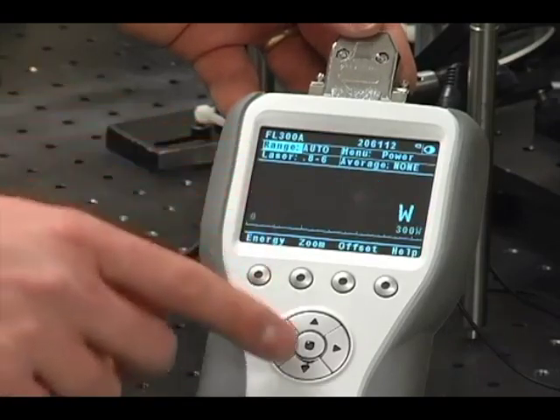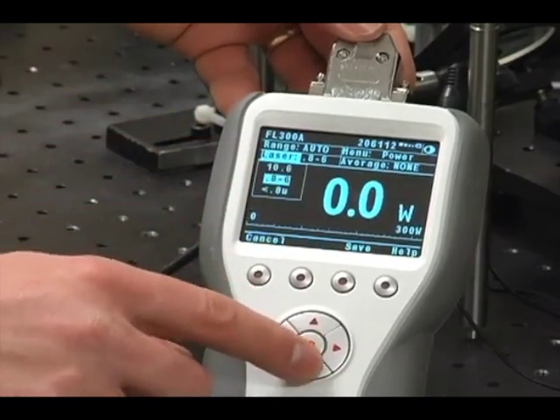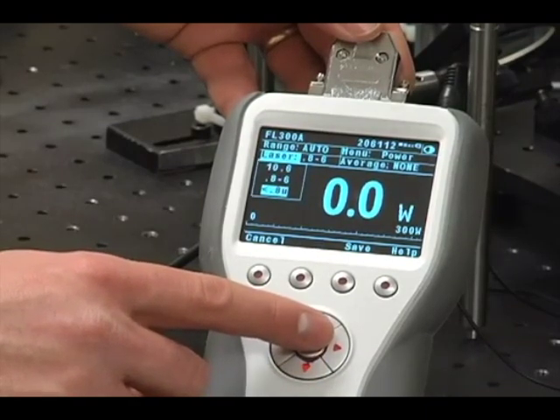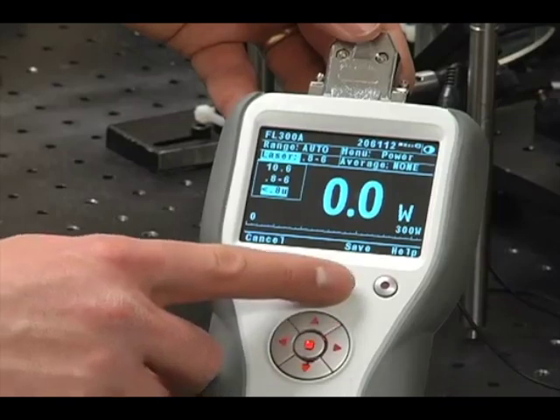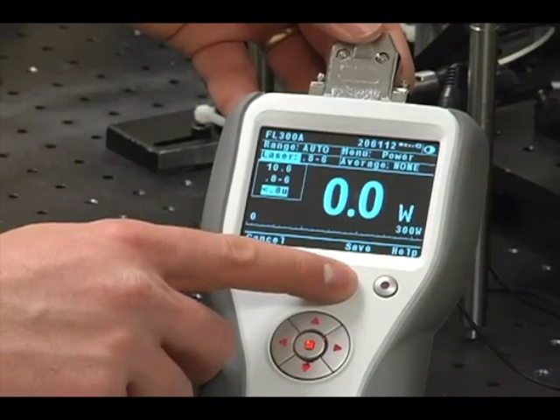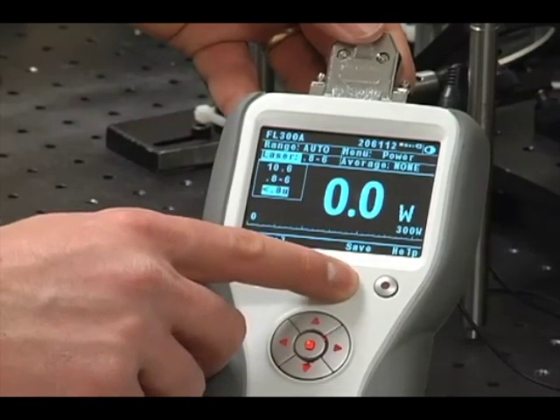Now we plug the smart head into the meter and turn on the meter. As you can see, the power range is on auto. Let's adjust to the proper laser wavelength. The laser we are using is wavelength 532, so let's set the wavelength to less than 0.8. If you want to save your settings, simply press save.